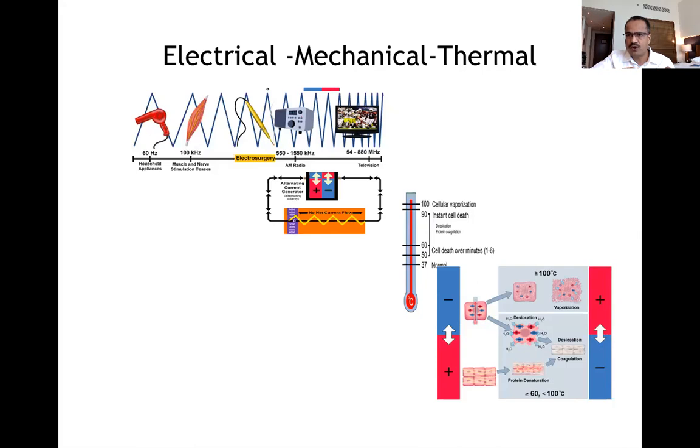This is not like a cautery because in cautery the metal instrument is heated and heat is transferred, whereas here you are not heating the tissues, you are just transferring the electrical energy. The tissues are moving so fast inside, in back they are actually hitting the tip of the instrument there. So this term is not to be used. We have to call it an electrosurgical unit.